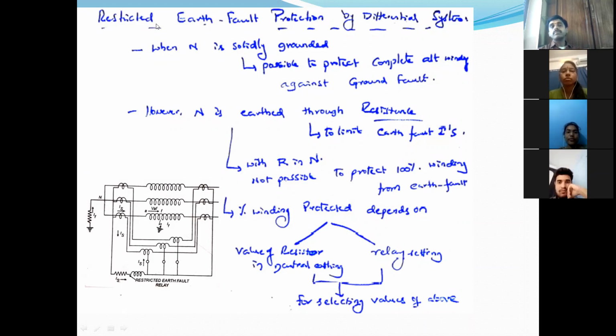That means not 100%. When the neutral is solidly grounded, it is possible to protect the complete alternator winding against ground faults. But when the neutral is earthed through resistance, to limit the earth fault currents, it is not possible to protect 100% of the winding from the earth fault. What is the percentage of the winding protected? It depends upon the value of the resistor in the neutral earthing and the relay setting. So these two are important aspects.